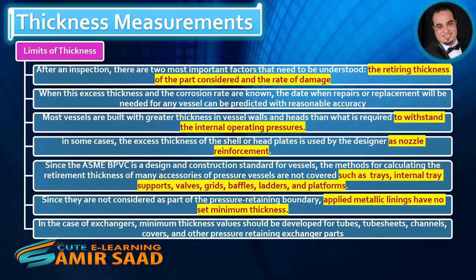Most vessels are built with greater thickness in vessel walls and heads than what is required to withstand the internal operating pressures. In some cases, the excess thickness of the shell or head plates is used by the designer as nozzle reinforcement. Since the ASME BPVC is a design and construction standard for vessels, the methods for calculating the retirement thickness of many accessories — such as trays, internal tray supports, valves, grids, baffles, and platforms — are not covered, as they are not considered part of the pressure-retaining boundary. Applied metallic linings have no set minimum thickness.